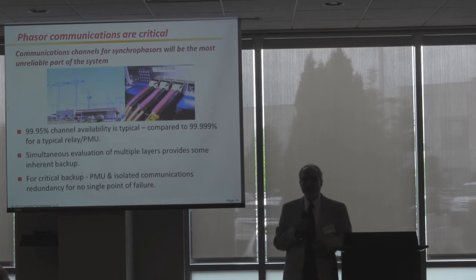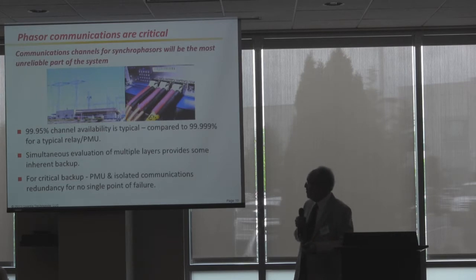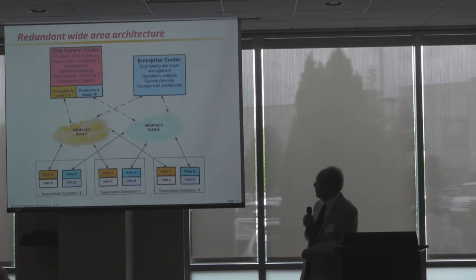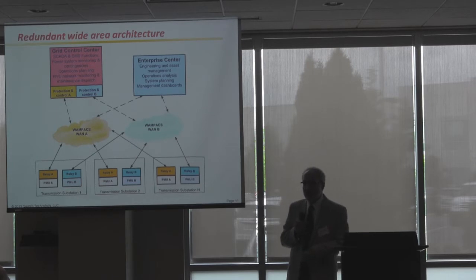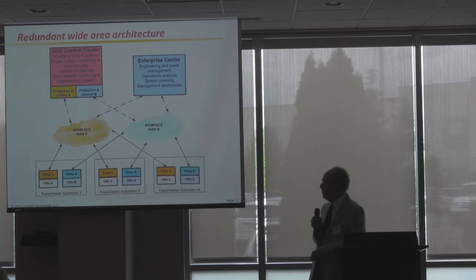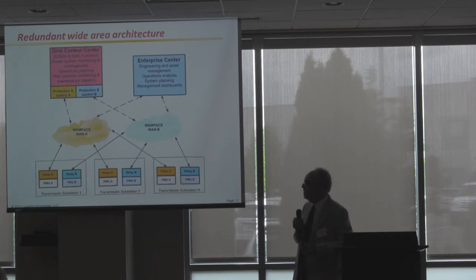Because we have layered backup possibilities with this methodology, even if we lose some of our communication paths at times, something will clear a fault. But for a really critical backup application, we're going to go to a redundant system. We show here an architecture for a WAMPAC that would do protection or even the control functions some of our speakers have been talking about today, with no single point of failure because we have redundant communications as well as PMUs and controllers that would do the fault protection.